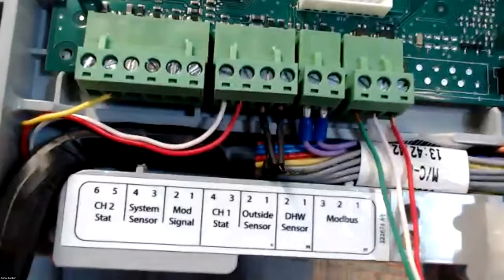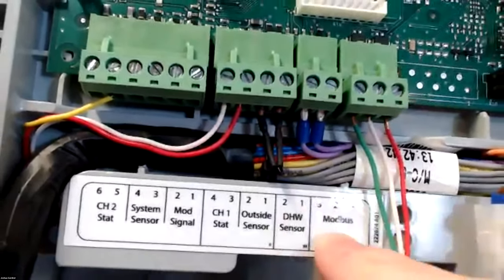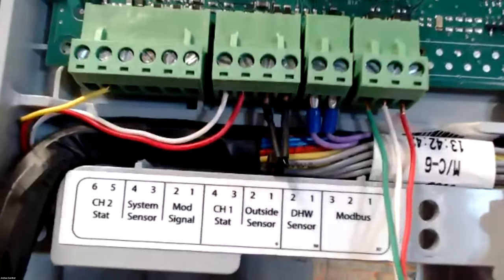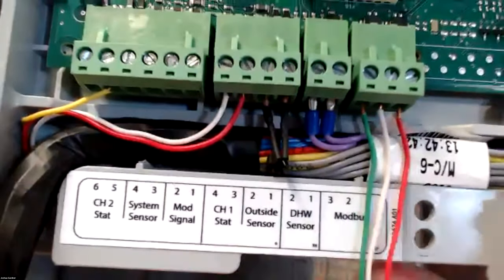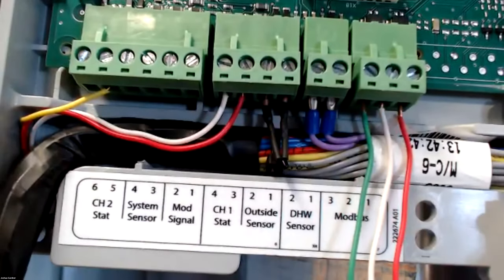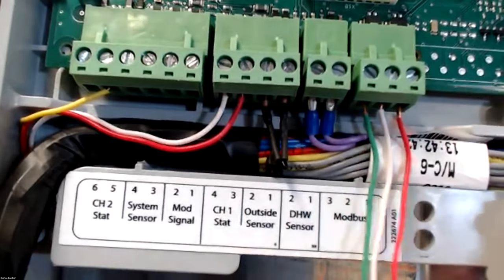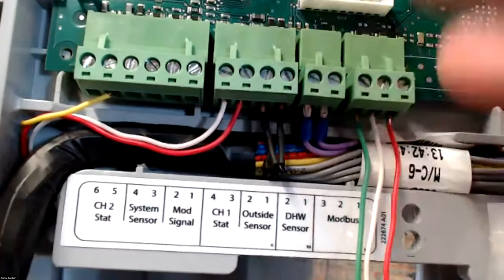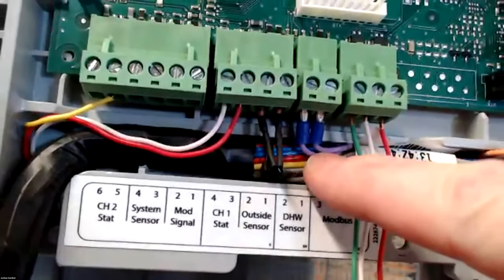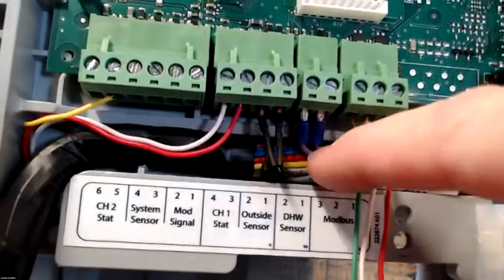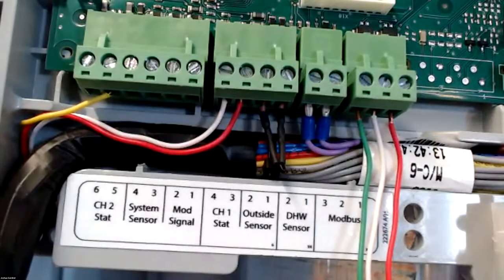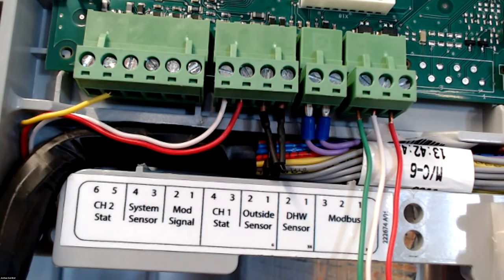So the first set of terminals working over here from the right, you have 1, 2, 3, the Modbus, this connection right here. This could be a commercial Modbus connection, or we're using it on this application for that add-on Wi-Fi module. 1, 2, 3. Then we have our domestic hot water connection. So if we're using a combi, this is already going to be field wired. All right. If we have a heat only, this won't be. We won't have anything in here. And this is where we either run an aquastat, so our Honeywell L4006, I think it is, aquastat, or we could run the 12K sensor that comes with the boiler. And then that will be our tank sensor.